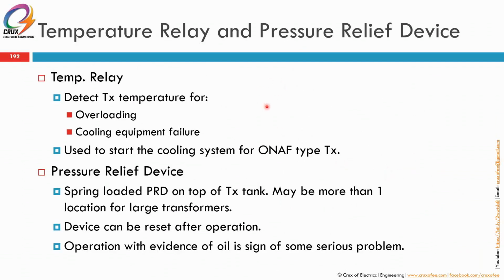temperature relay and pressure relief device. So we have temperature relay, which is to detect transformer temperature for overloading and also cooling equipment failure. So this is an indirect finding of a cooling equipment failure. Obviously, if the transformer temperature is going up, there could be some problem with your cooling equipment. It is also used to start the cooling system for ONAF type transformer. If you have a transformer with ONAF configuration, which is oil natural air forced, the temperature relay is used to start the cooling fans or the cooling system.